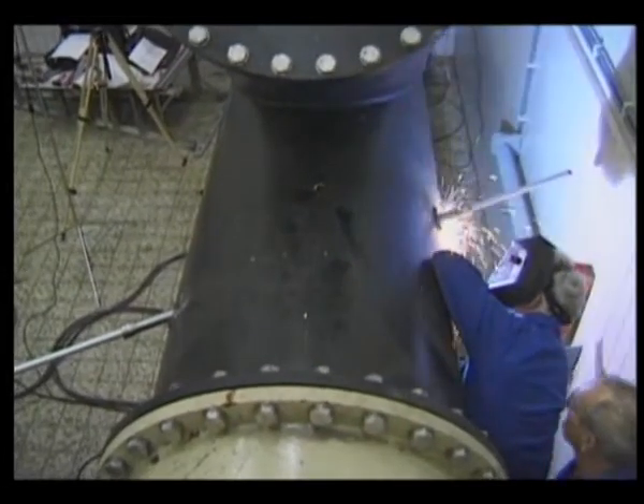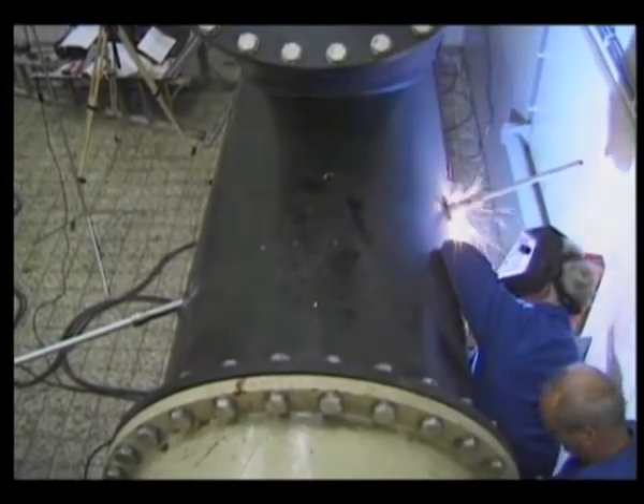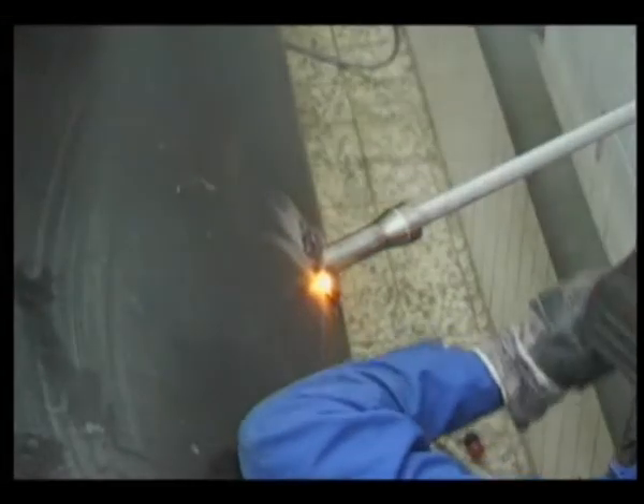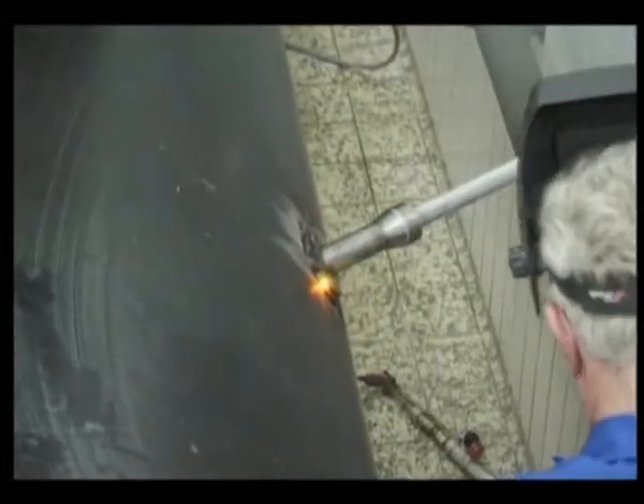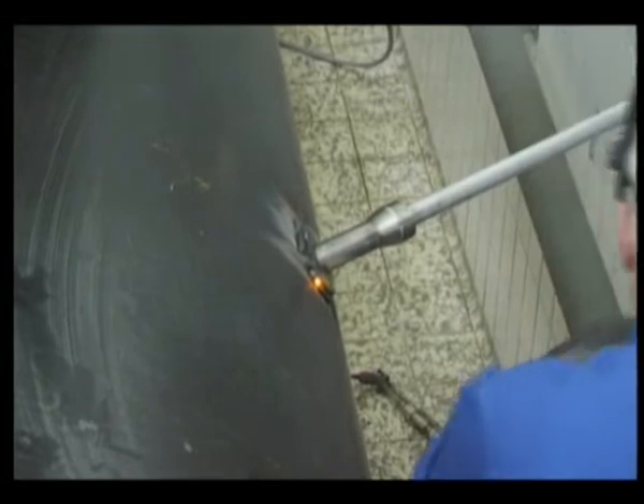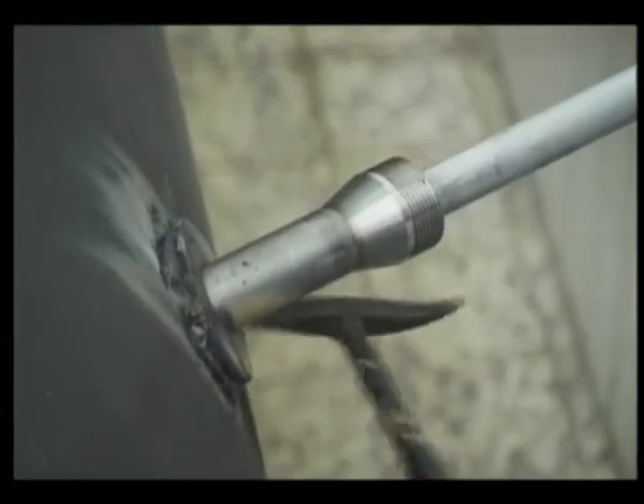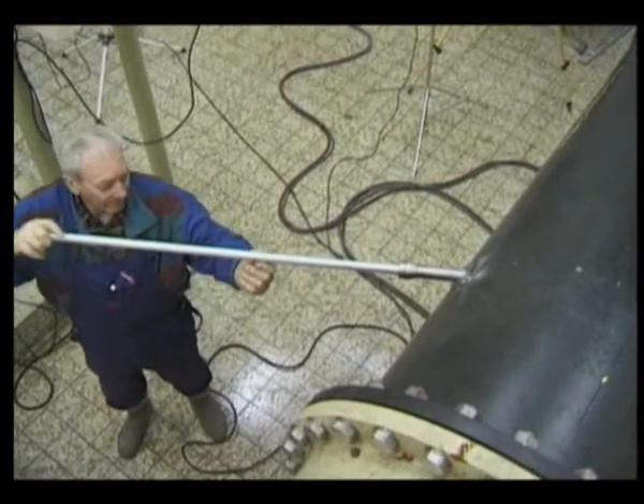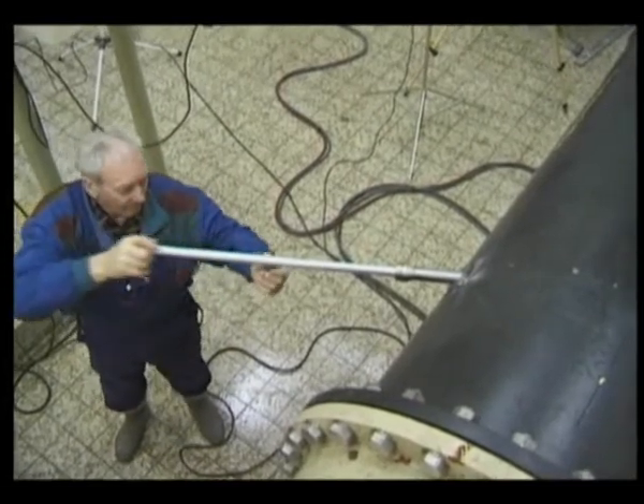When the alignment rods and the transducer holders are in the right position, you can weld the mounting plates all the way round. Make sure that only the mounting plates are welded. When the mounting plates have been welded on, it must be checked that everything's in the right position.